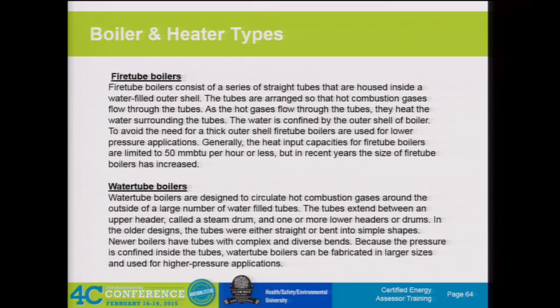So boiler and heater types: the combustion process is driven to support some sort of beneficial function that we need—we're trying to get the heat out of the unit. In general, there are two different types of heat transfer designs: fire tube boilers and water tube boilers. In fire tube boilers, the combustion gases are in the center areas of the heat exchanger, with a water-filled section surrounding these tubes. The heat transfer is from the tube out into the water bath section. These fire tube boilers are generally smaller sizes, and we don't see a whole lot of them.